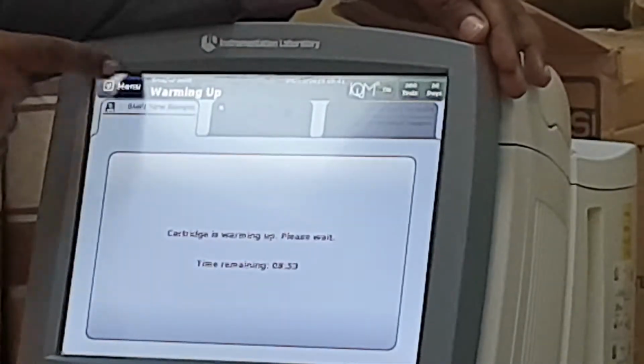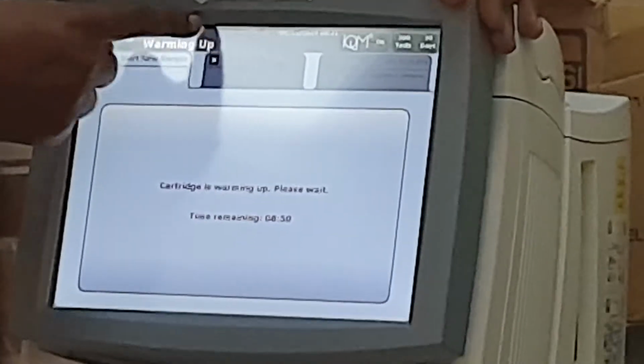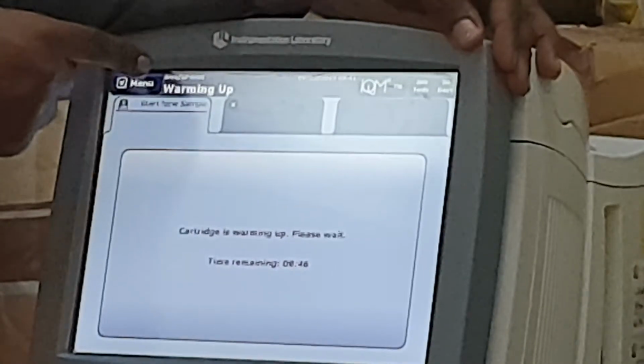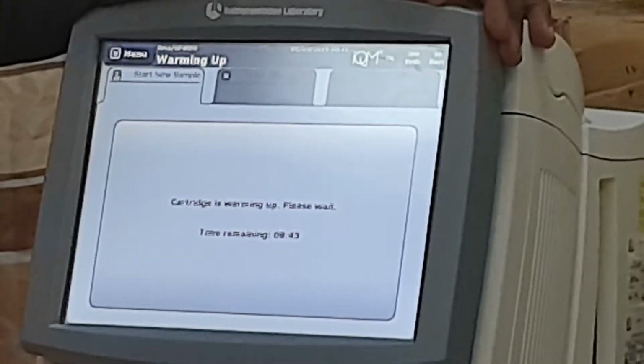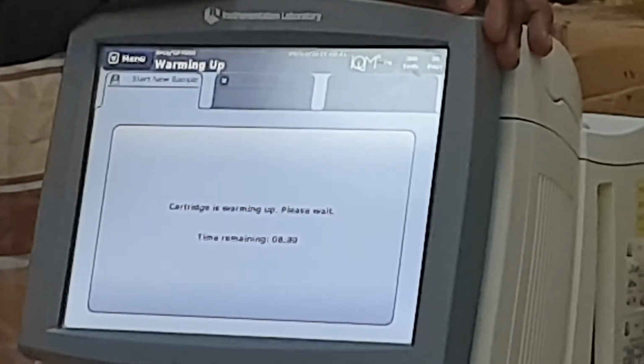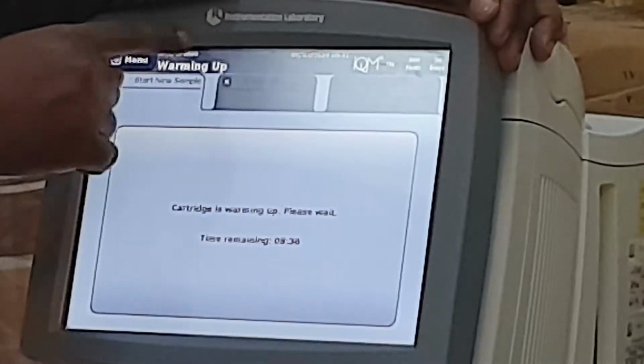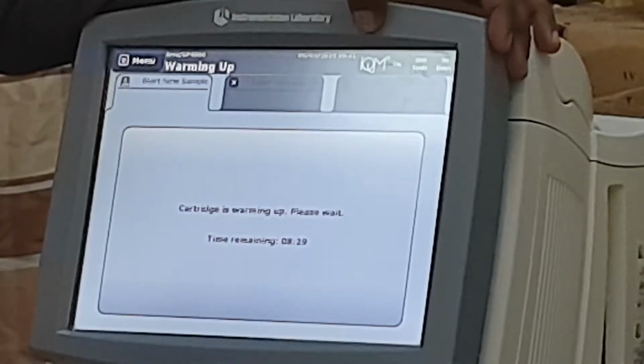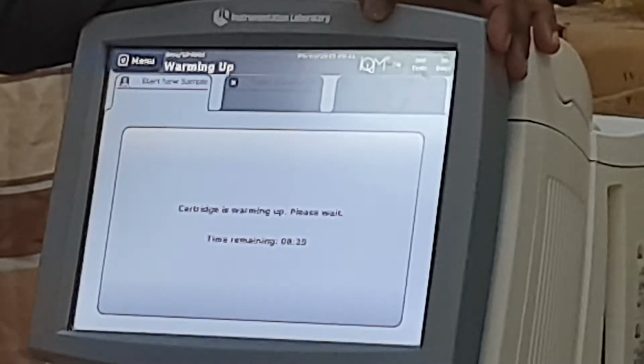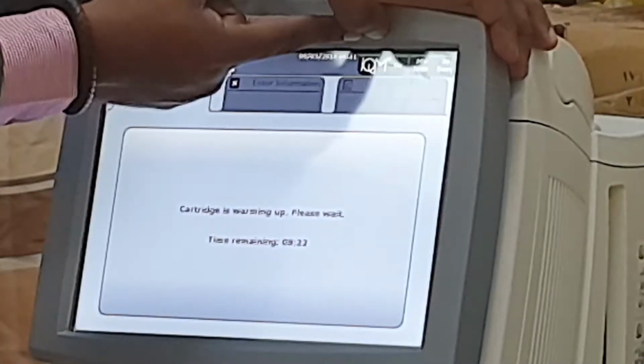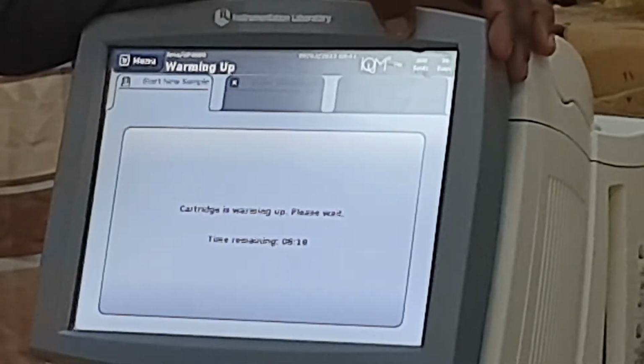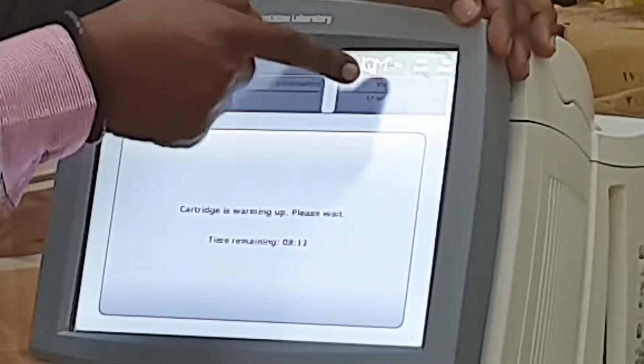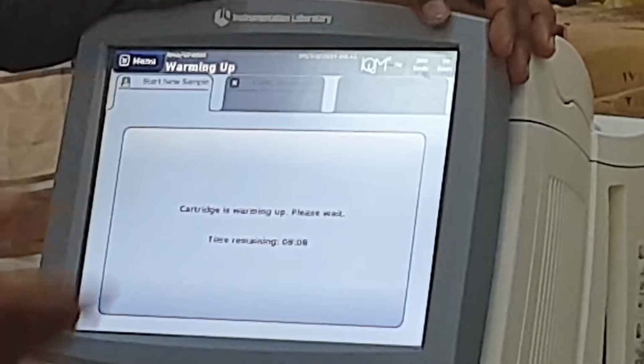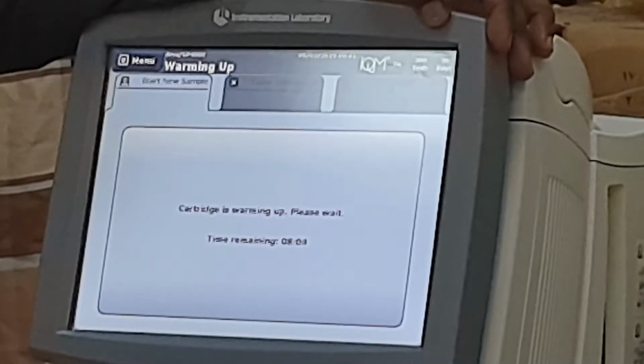At the top, you will find the menu, and we will talk about the menu also. Here is the status of the machine. If it's ready, that means I can run a sample. If it says IQM processing, that means the machine is running control now. And the name of the machine, the date and the time are here. If this one is green, that means it's okay: the IQM is not running now. But if it's yellow, that means you cannot run a sample because the control is running now. And the last thing, the days remaining and the tests remaining. 300 tests means I did not use anything. 30 days means 30 days remaining for you. Very good.